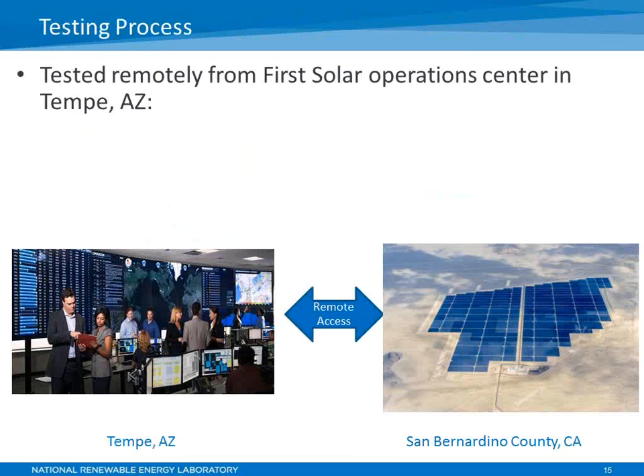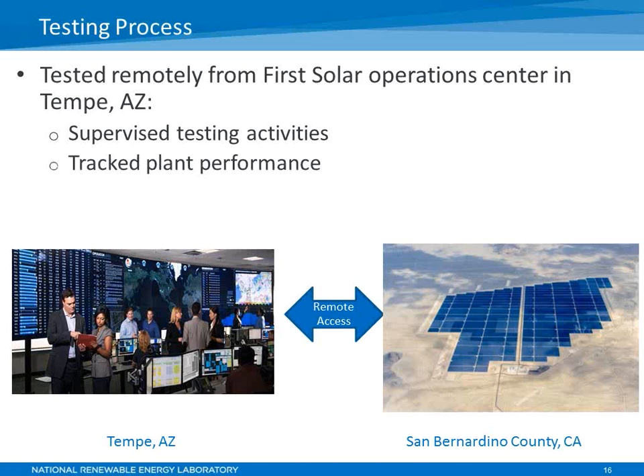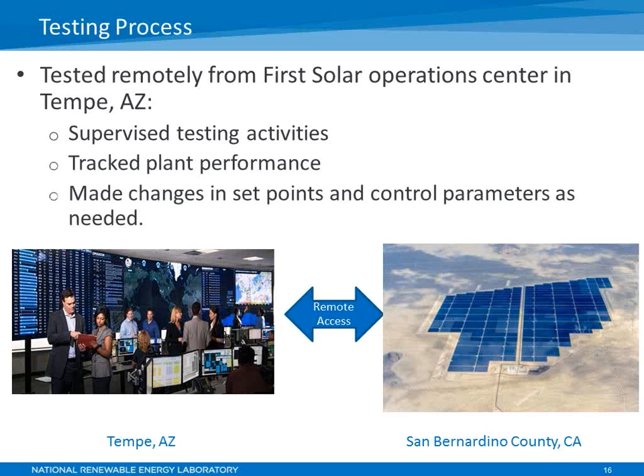With that in mind, the way we carried out this test was from a remote center, which is located in Tempe, Arizona. This is the picture of the remote center. From that, we can access this plant, which was in San Bernardino County in California, and remotely we can supervise the testing activities. We had both the CalISO and NREL teams there, and they would suggest, how about performing this test versus that test? And we could carry out those tests, see the results, and collect the data. We tracked the plant performance using that approach, and where necessary, we made changes in the set points and control parameters as needed.